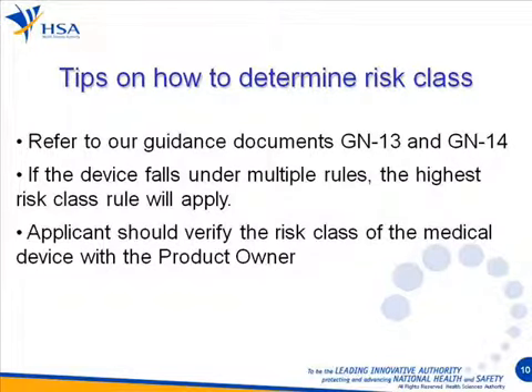So the tips to determine the risk class: always refer to our guidance documents. If the device falls under multiple rules, the higher risk class will always apply. And you should always verify the risk class with the product owner of the medical device, and we advise you to let them have a copy of our guidance documents so that we can clarify this with you.